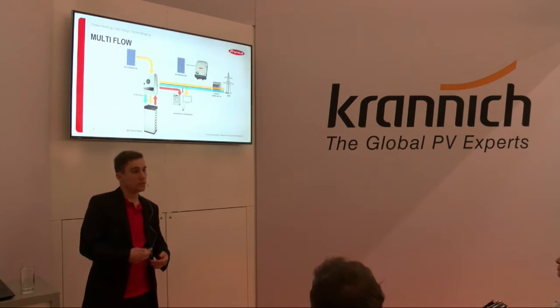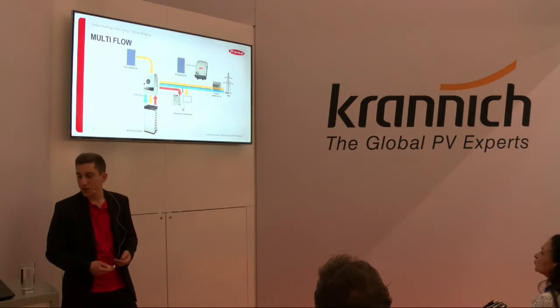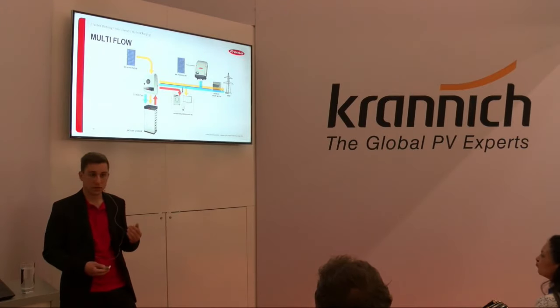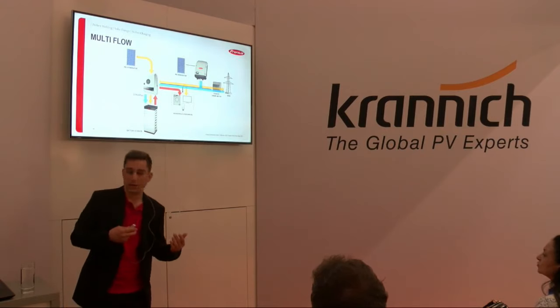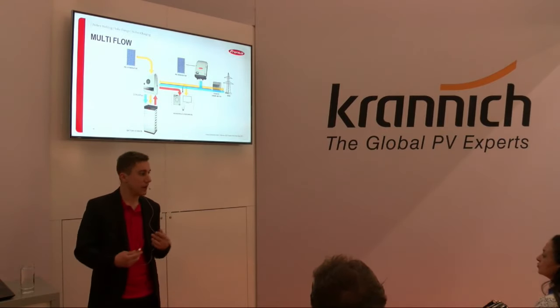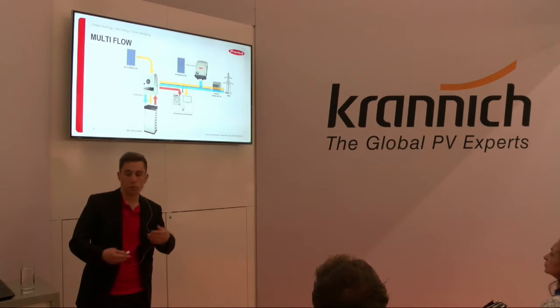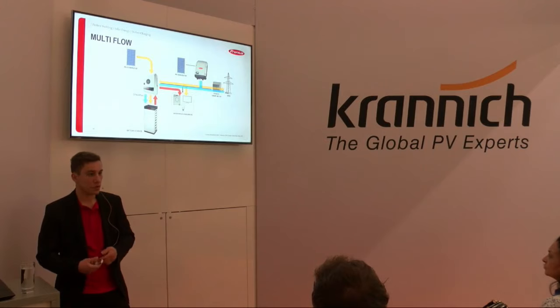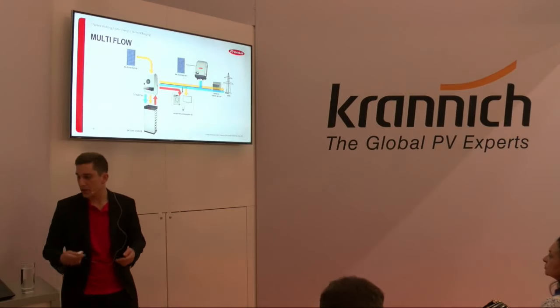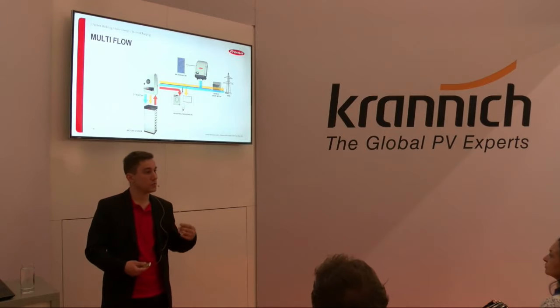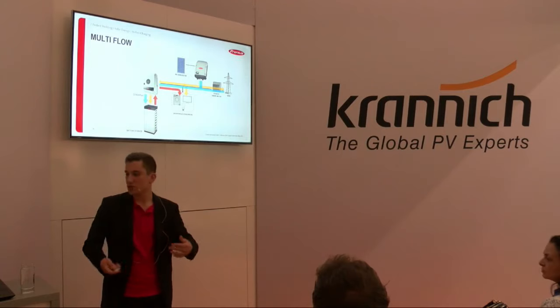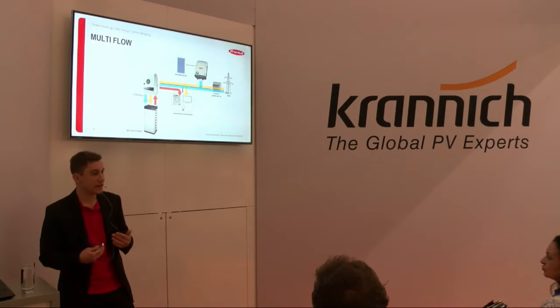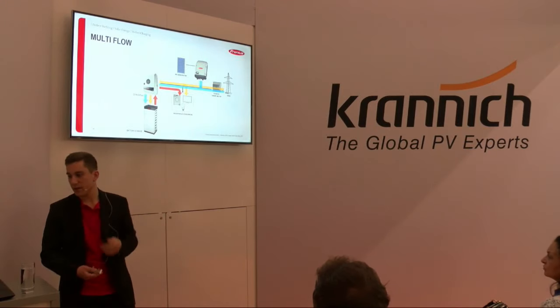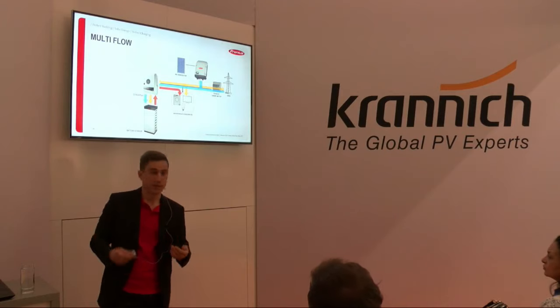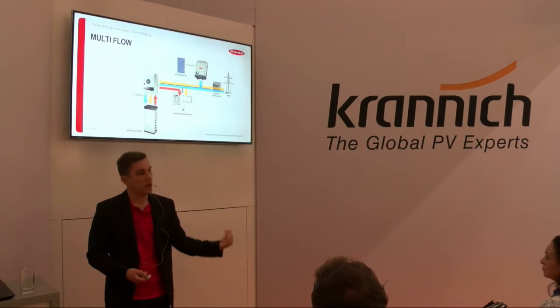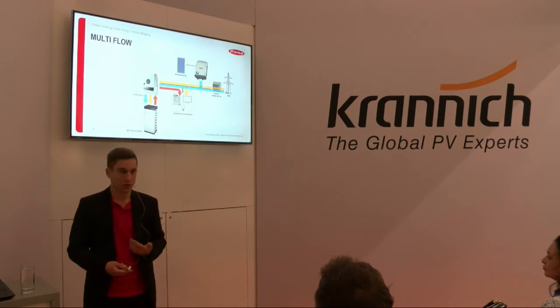Furthermore, it's possible to do AC coupling. If you have an existing inverter, you can connect it to the new system. So if you have, for example, a normal Symo hybrid device, you can connect it with the GEN24 device and do repowering with a battery system. Repowering is always possible, and then you can do AC coupling - you don't need to put panels on the GEN24 device, you just do the AC coupling with your existing device, put your energy loads coming from the existing inverter to store energy in the battery system, and then retake the energy from the battery system for your household consumers.